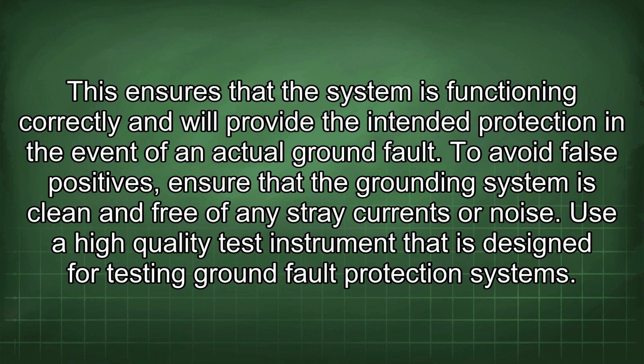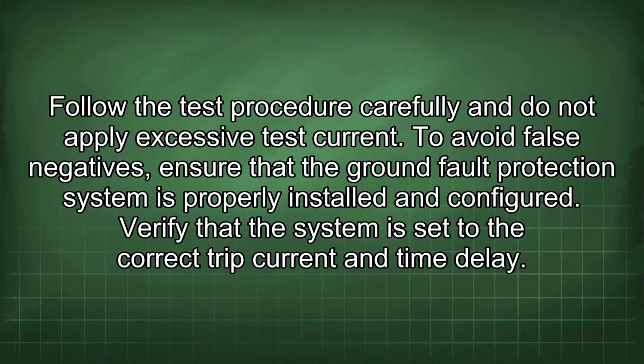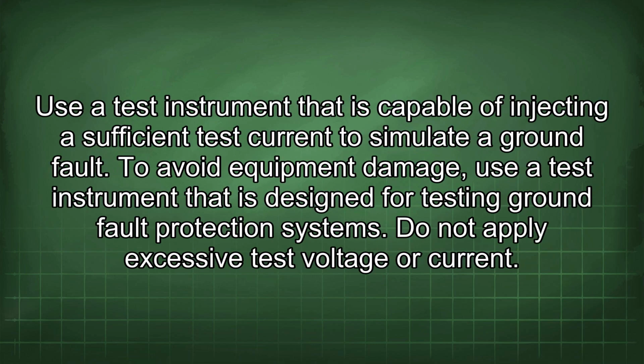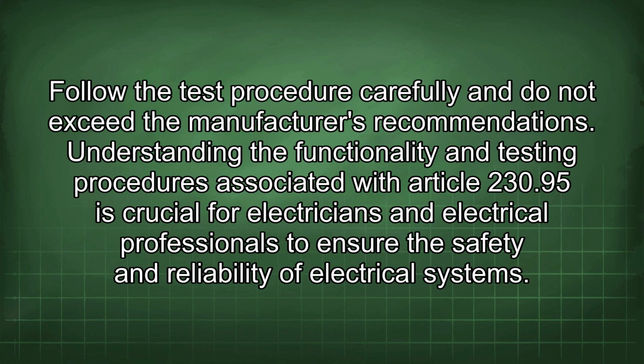To avoid false positives, ensure that the grounding system is clean and free of any stray currents or noise. Use a high-quality test instrument that is designed for testing ground fault protection systems. Follow the test procedure carefully and do not apply excessive test current. To avoid false negatives, ensure that the ground fault protection system is properly installed and configured. Verify that the system is set to the correct trip current and time delay. Use a test instrument that is capable of injecting a sufficient test current to simulate a ground fault. To avoid equipment damage, use a test instrument that is designed for testing ground fault protection systems. Do not apply excessive test voltage or current. Follow the test procedure carefully and do not exceed the manufacturer's recommendations.